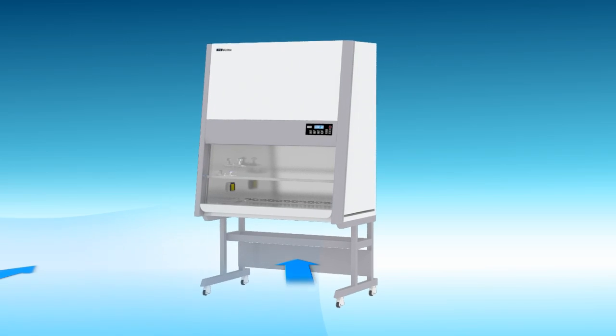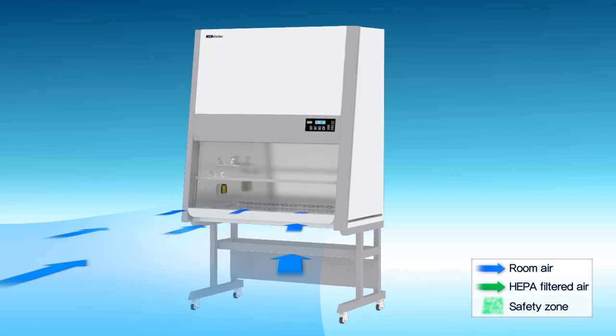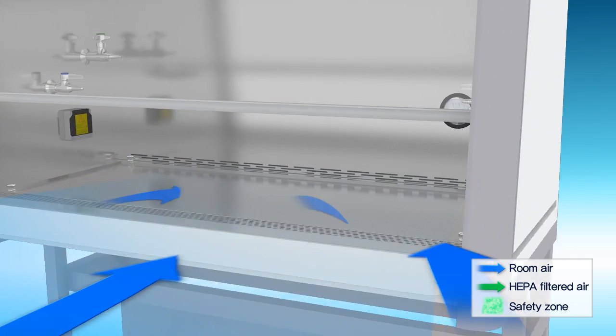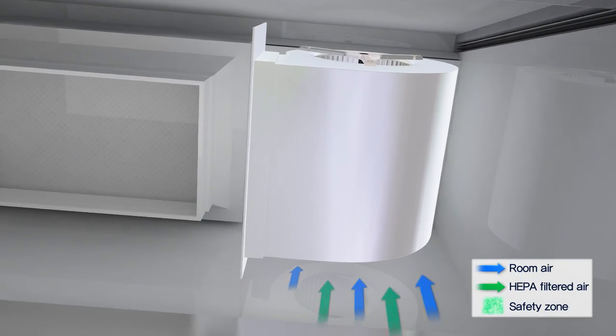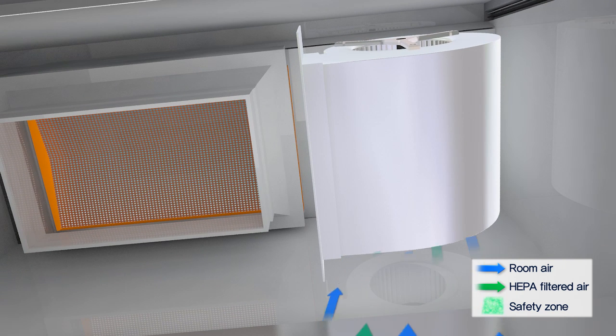As the blower, which is basically built into upper part of the cabinet operates, the room air enters inside the cabinet through intake grill. The incoming air moves to the plenum located on the backside through underneath work surface and rises up to the blower.